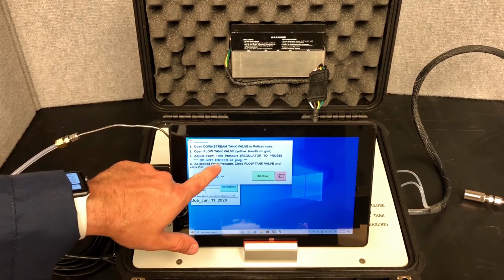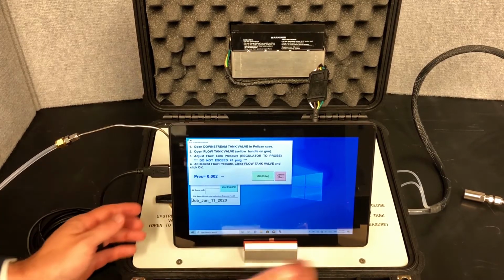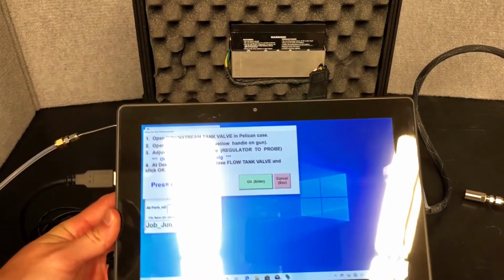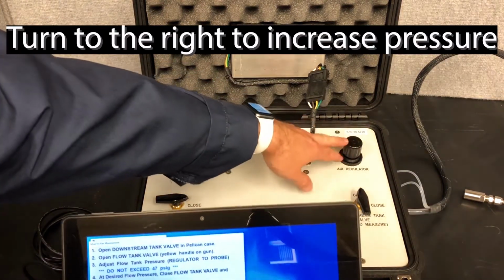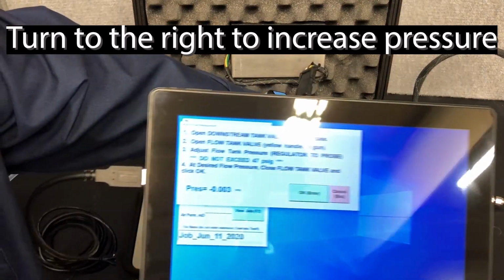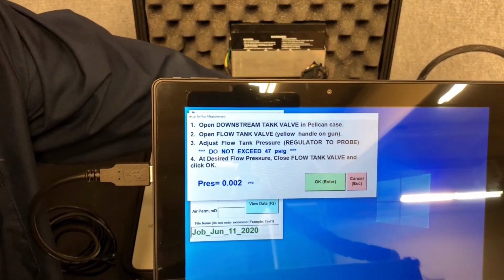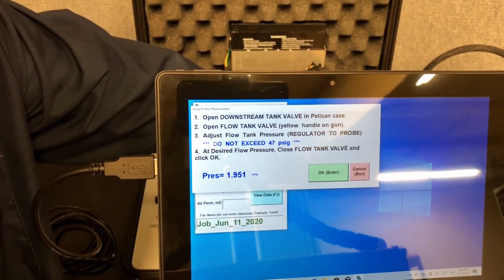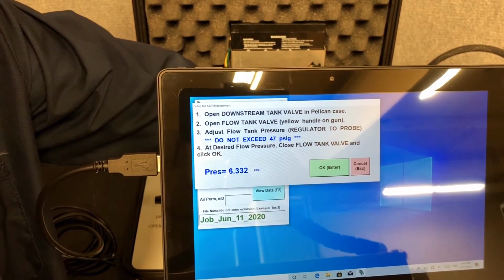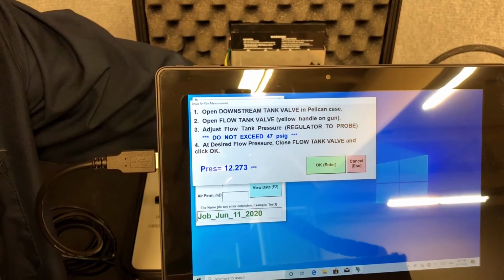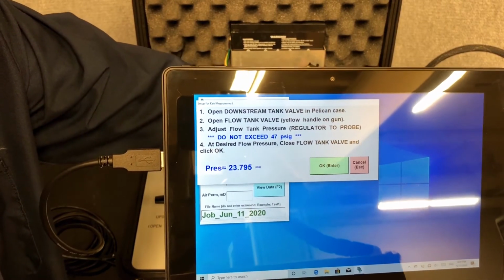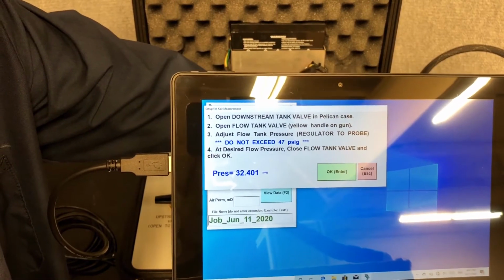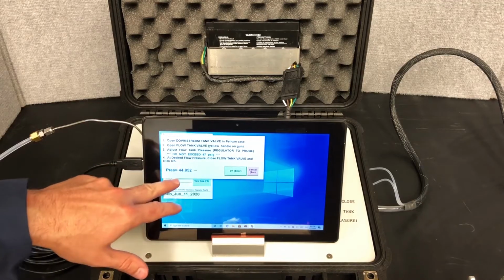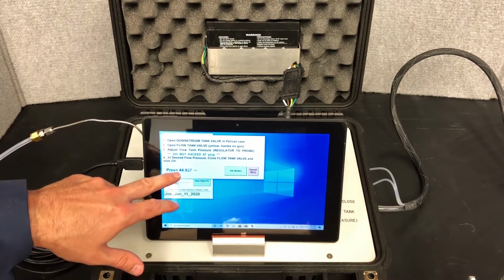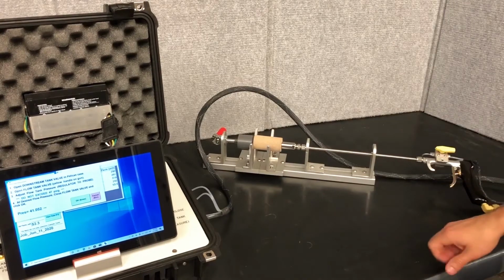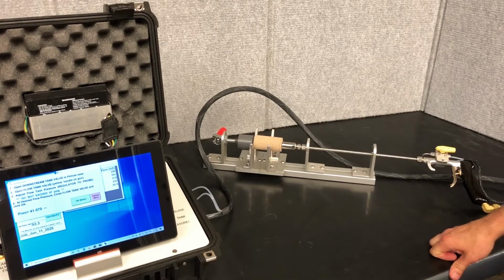Step 3 is adjust flow tank pressure regulator to probe. I'm going to lift this up to show you guys - this is your actual regulator for step 3. So if you watch, we'll pressurize it. Once you get to that, you can't go above 47; most tests will be around 40 or so. Once we get to an actual desired pressure, right now it's at 41.065.